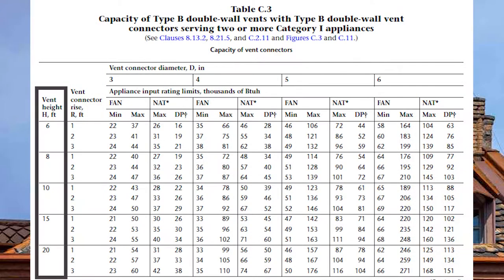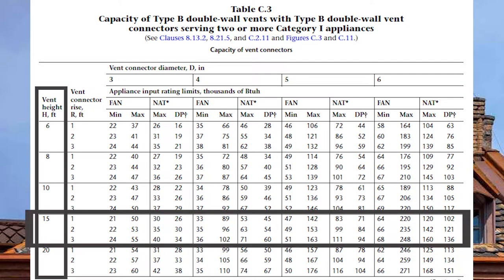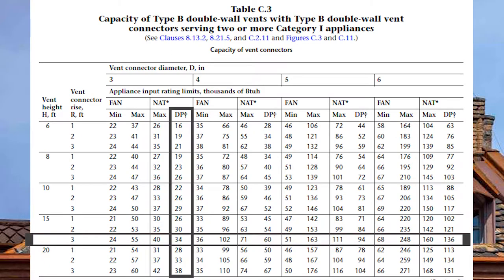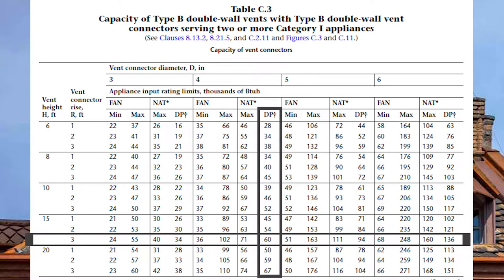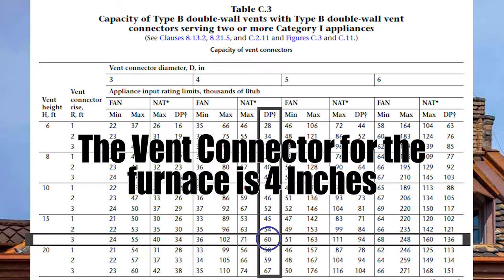Next I'll size the furnace. Coming down to the 15-foot vent height and across at a three-foot vent connector rise, I go to NAT DP. The three-inch area is only good to 34,000 BTUs, but the four-inch area is good to 60,000 BTUs. Four inch will be the size of my vent connector for the draft hood equipped furnace.